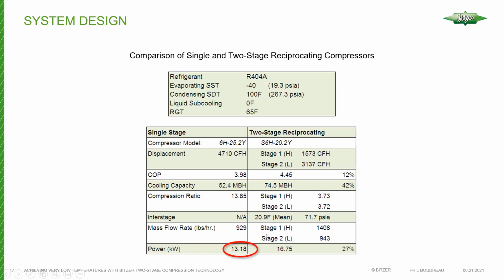Power in kilowatts for the single stage is 13.18. And then when we go to the two stage, it's 16.75. So it's just, again, we don't get something for nothing. So the power increase is 27%. However, there's a big difference in capacity.